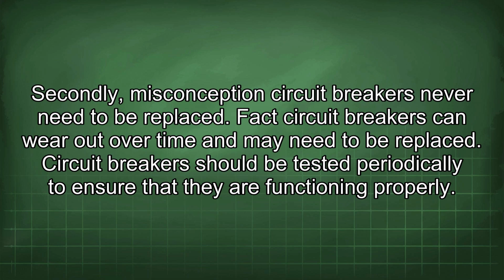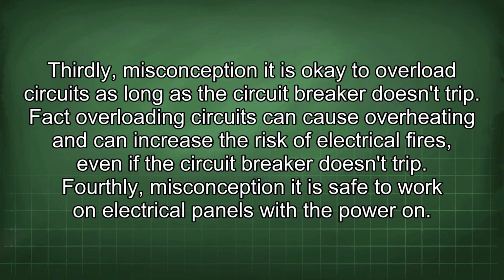Secondly, misconception: circuit breakers never need to be replaced. Fact: circuit breakers can wear out over time and may need to be replaced. Circuit breakers should be tested periodically to ensure that they are functioning properly. Thirdly, misconception: it is okay to overload circuits as long as the circuit breaker doesn't trip. Fact: overloading circuits can cause overheating and can increase the risk of electrical fires, even if the circuit breaker doesn't trip.